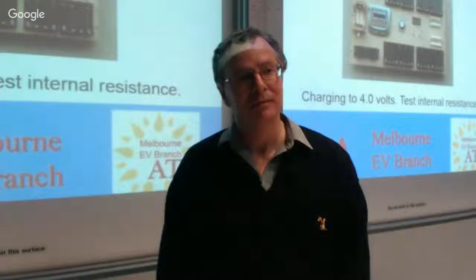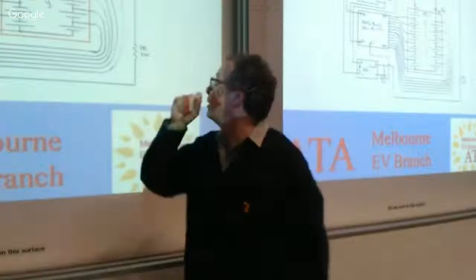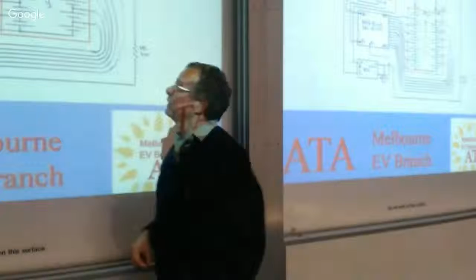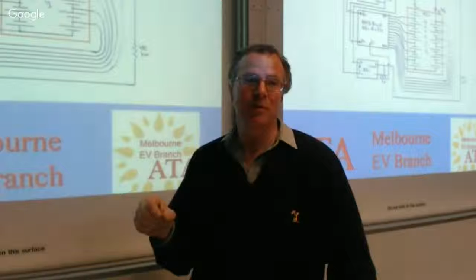If you use just a series configuration of battery, what capacity does that produce roughly? It depends on the capacity of each block. A 48-volt battery is 13 in series, and depending on how many cells you have in parallel we could go through the maths. For a home battery system you probably want 3 kilowatts as a minimum, a 7 kilowatt home battery system would be good. Divide 7 kilowatts by 48 volts and that gives you the number of ampere hours for the battery. Ampere hours is what we're looking at, and that's just multiple cells in parallel, a block made up of multiple cells.